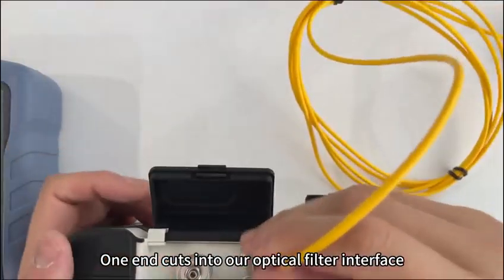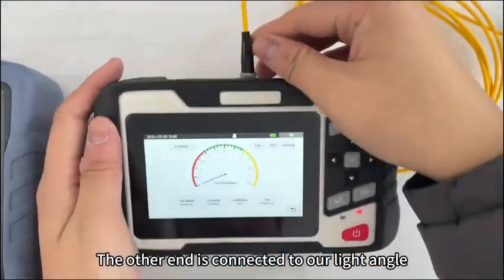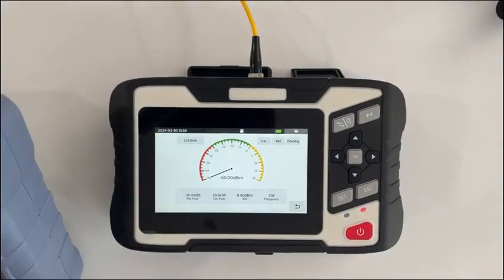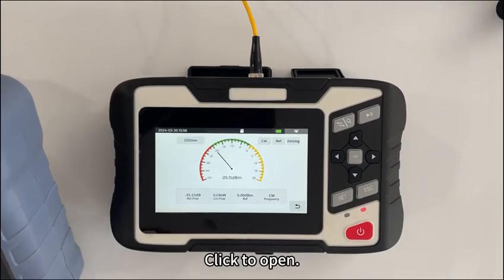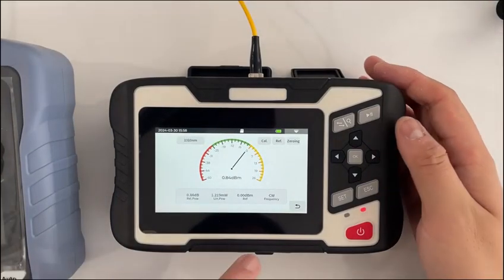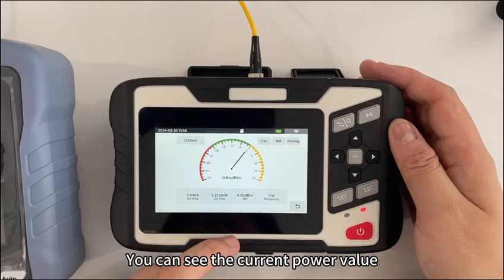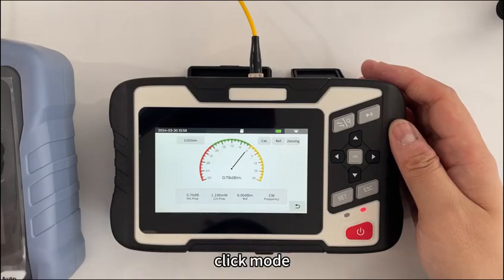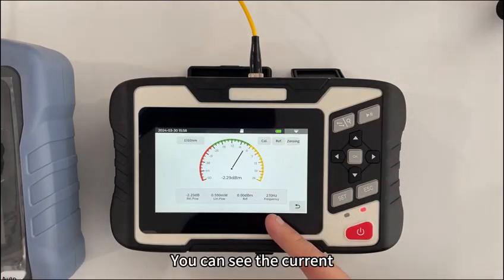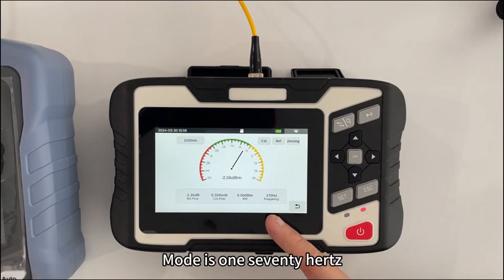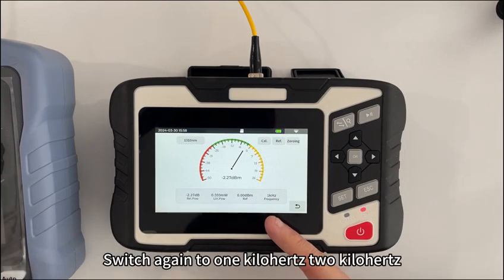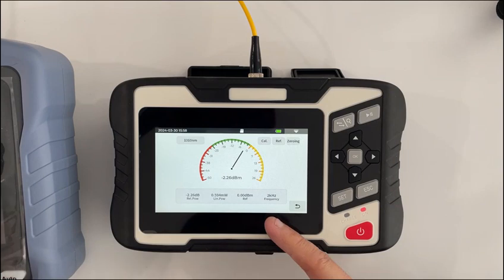One end plugs into our optical power interface. The other end is connected to our light source. Click to open. You can see the current power value. Click Mode. You can see the current mode is 270 Hz. Switch again to 1 kHz.